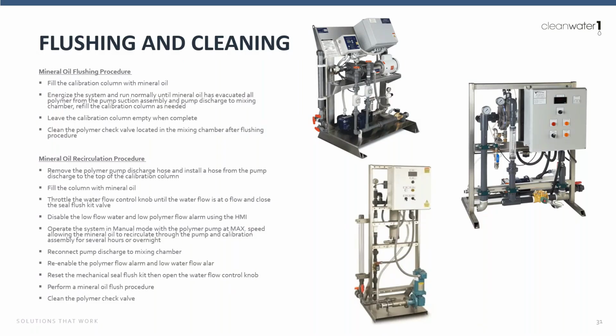Again, this is relatively easy to do, but it's really important, especially on shutdown. What we can do is we can fill the calibration column, which you'll see on the left-hand side of those first two skids, and on the skid on the right is in the back. You fill that with mineral oil, and there's a couple ways to do it. You can isolate the polymer inlet and open up the calibration column and pump the calibration column through the neat polymer metering pump. Generally, you're going to want to do that a few times to flush everything out.